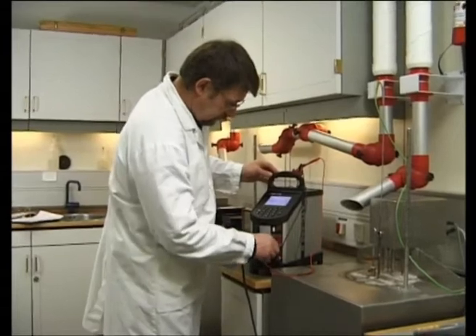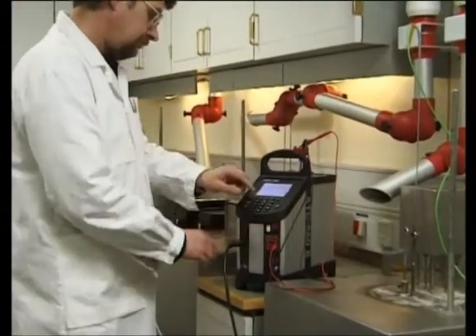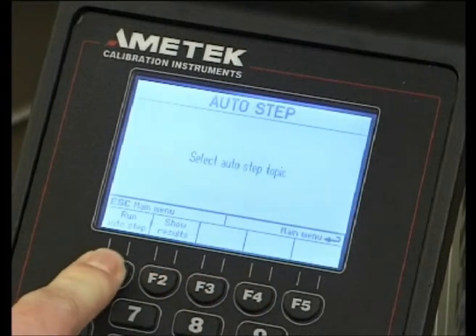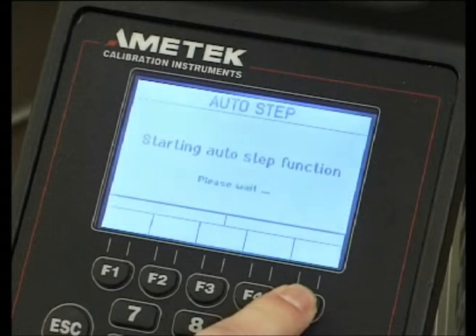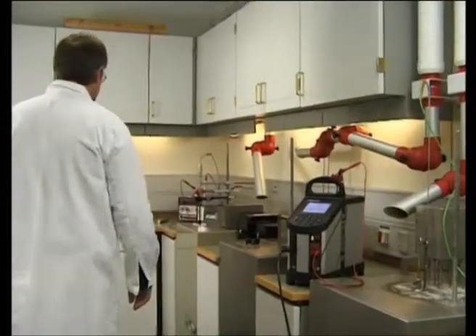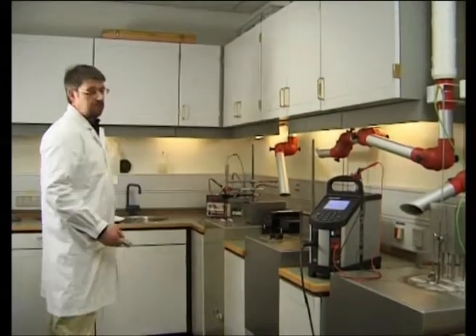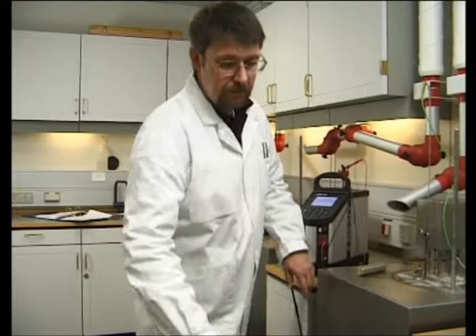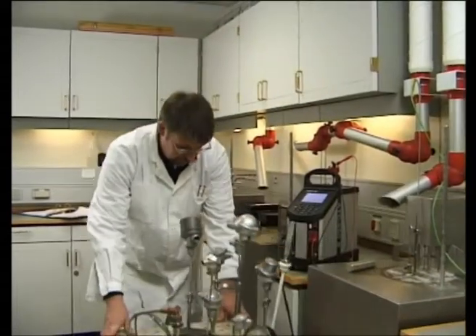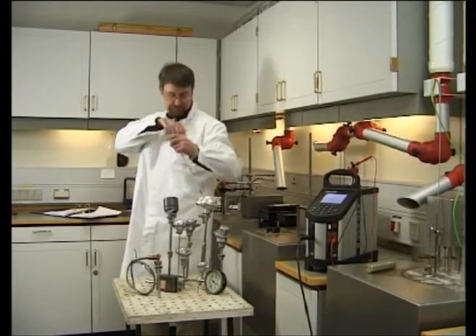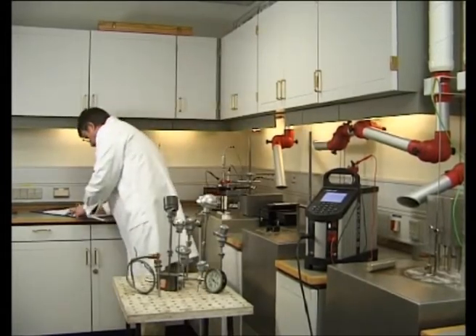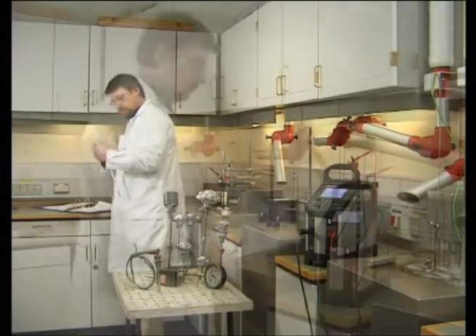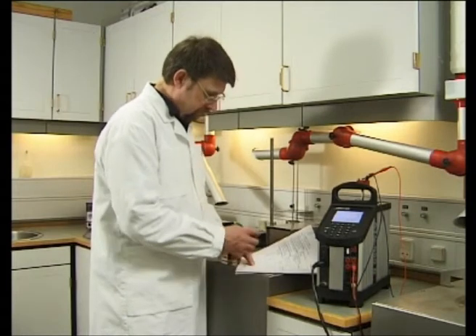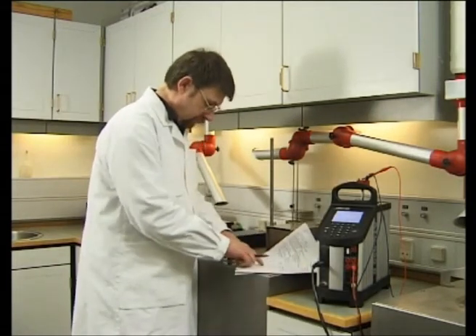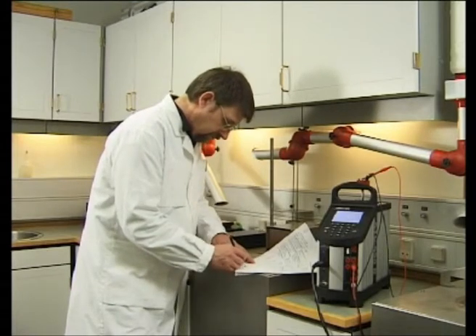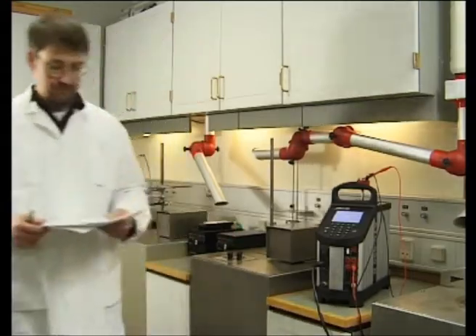Regardless of whether you calibrate in the workshop or in the calibration laboratory, the Jofra ATC series saves you time by automating your calibration routines. The ATC series has a built-in amplifier that can measure all temperature sensor types: resistance thermometers, transmitters, milliamps, thermocouples, voltage, and thermostats. With the calibrator programmed for automated calibrations, you can leave the ATC calibrator and turn your attention to more pressing tasks. All data is stored, allowing you to print the certificates at an appropriate time. You save both time and money on manpower and technical resources by using our complete integrated solution.